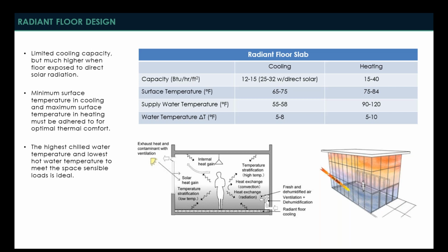A normal cooling coil might have a chilled water delta T between 10 to 14, sometimes up to 16 degrees. For these radiant systems, you're getting a smaller delta T, usually between 5 and 8 degrees. On the heating side, you're looking at somewhere between 5 and 10 degrees. So the important thing when we're talking about these water temperatures is, again, you want to be able to use the highest chilled water temperature that you can and the lowest possible hot water temperature that you can to meet the space loads, the space sensible loads. That's the ideal scenario.